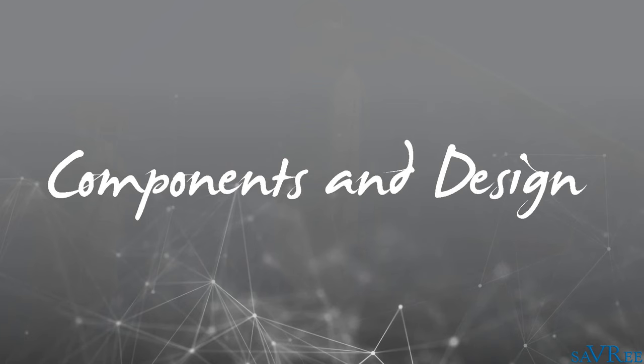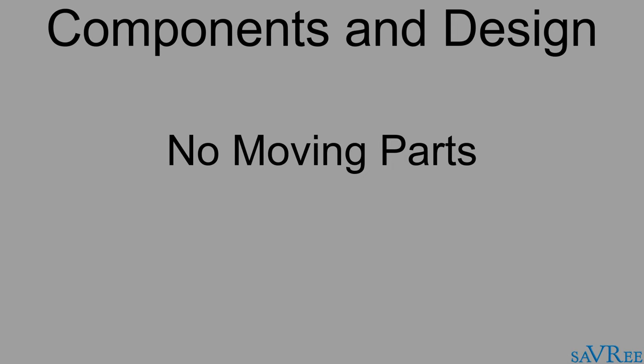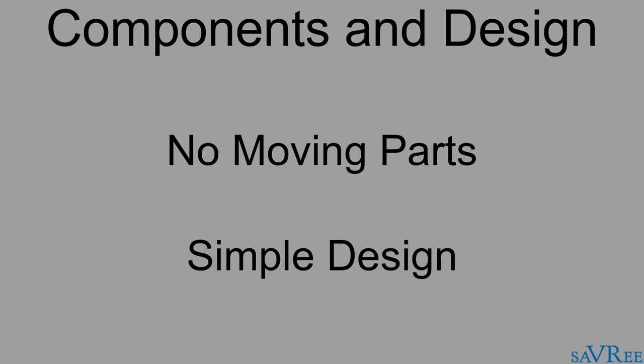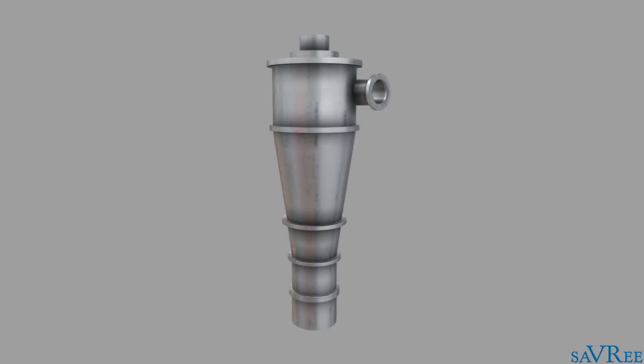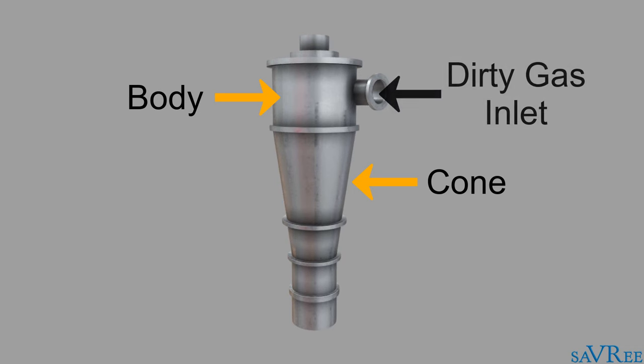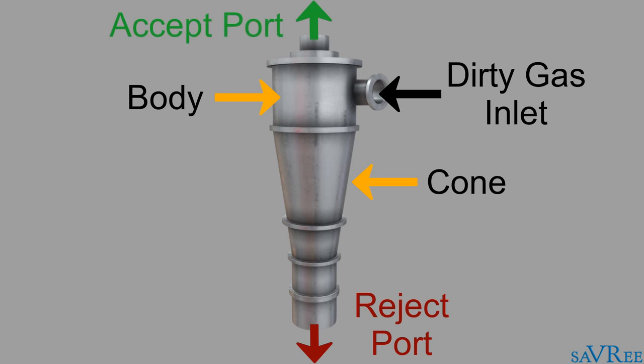A reverse flow cyclone separator is an industrial assembly with no moving parts and a simple design. The main cylindrical part is known as the body or barrel. The gradually narrowing conical section is known as the cone. Untreated gas enters tangentially through the inlet at the side of the separator. Entrained particles within the gas stream are separated and discharged through the reject port at the base of the separator. Clean gas exits through the accept port at the top of the separator.